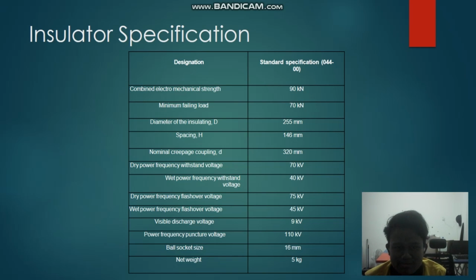For the insulator specification, the nominal creepage coupling of our insulator is 320 millimeter. The minimum failing load is 70 kilonewton. The combined electromechanical strength is 90 kilonewton. The radio interference is 2.5 milliamp. The dry power frequency flashover voltage is 75 kV, and others.